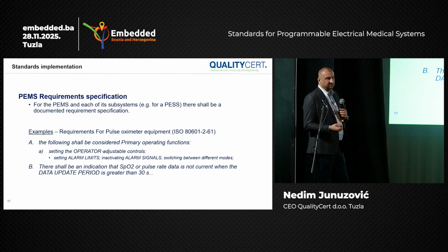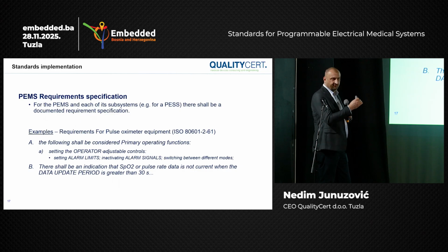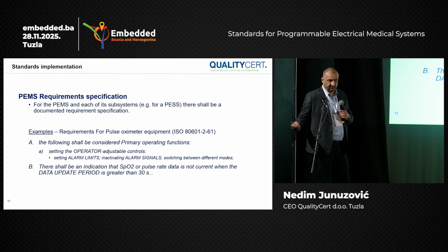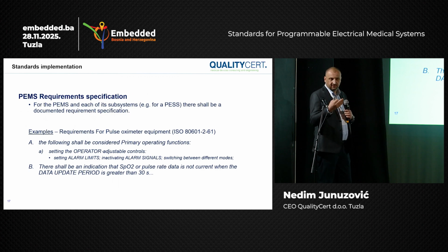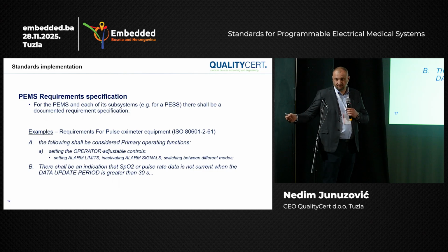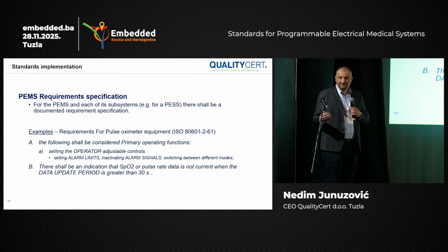The requirement specification is also a key stage in development work. Hypothetically, if you miss including some requirement in your portfolio or list, and you implement the product, most likely when you get to the stage of testing against some standard, it will show you are missing requirements that you didn't consider at the beginning. That means you fail the test because you are missing requirements from the standard. So to avoid this, please put really good effort into compiling a valid and comprehensive requirements document and requirement list for your product.